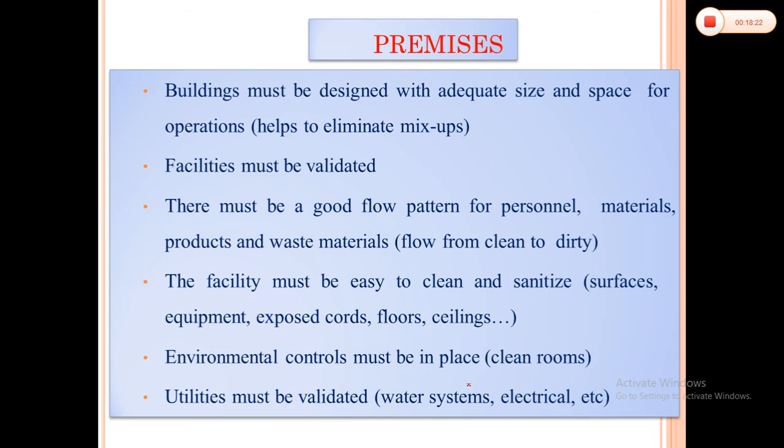Some mechanical servicing, like electrical, gas, water, air ventilation. As I use the word utilities here, these must be validated. Obviously the lines into this area must be carefully planned. One of the most effective plans is to provide a floor above, space beneath, or a corridor alongside the production area where all the service connections can be accessible and properly maintained. This will prevent interruptions of production and, most importantly, contamination of the production area by maintenance operations and persons.